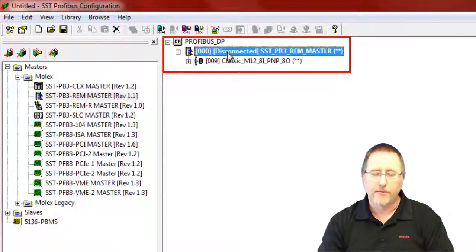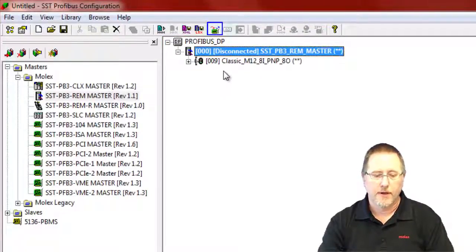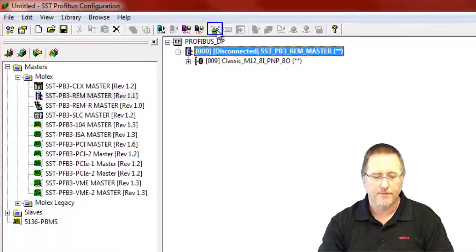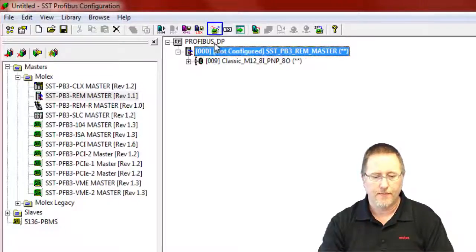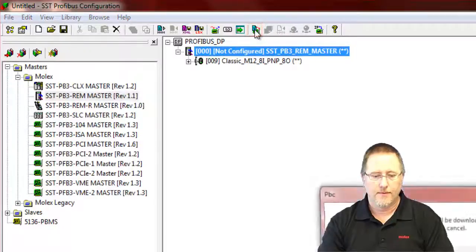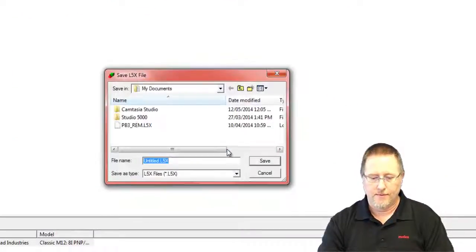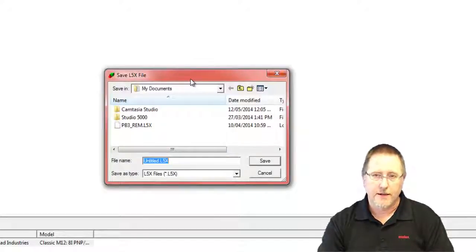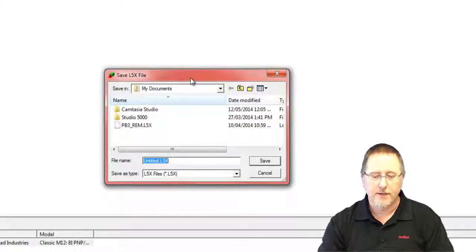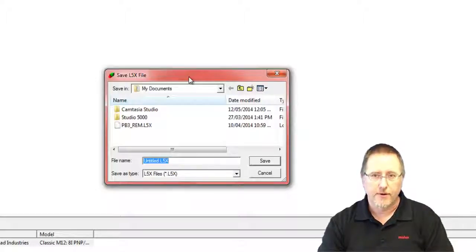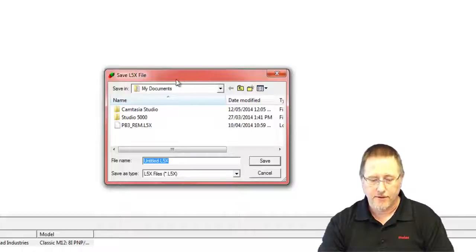And now what we want to do is connect to the module and download the configuration and put it online just to test to make sure the communication is all good. Now when we do this, because it's the first time, it asks us to save the L5X file. This is going to be the add-on instructions and tags that we're going to import into our logic software that will match up with our configuration here.